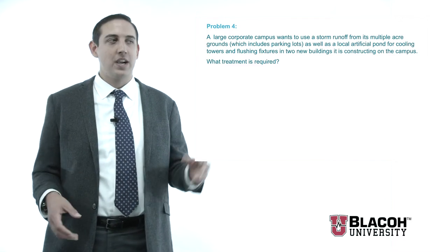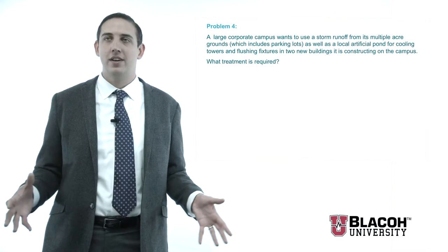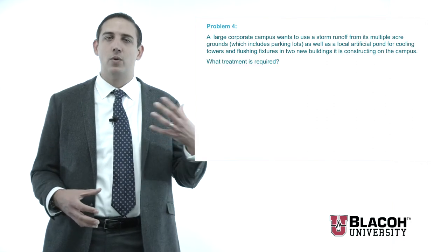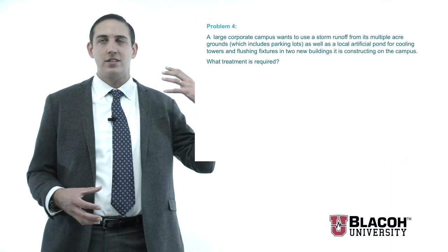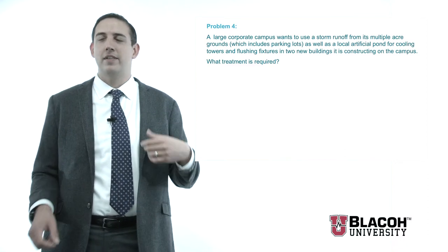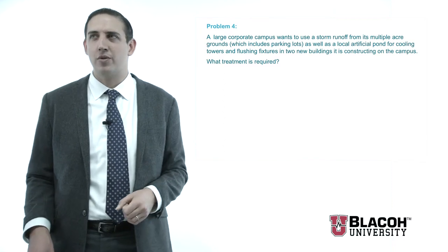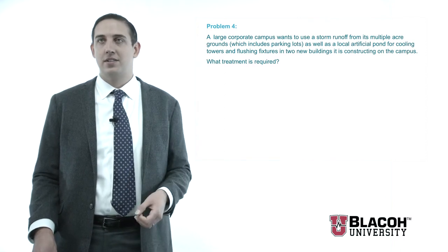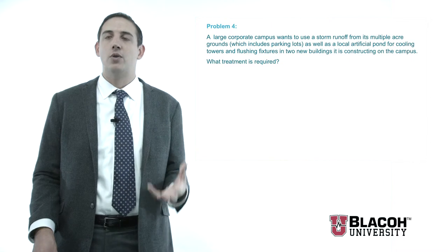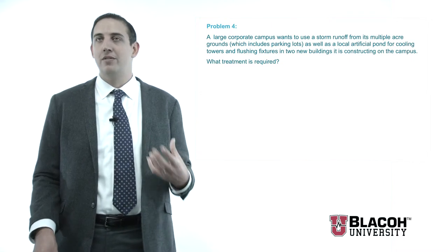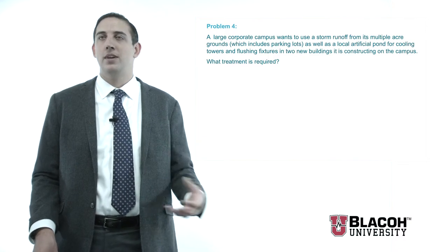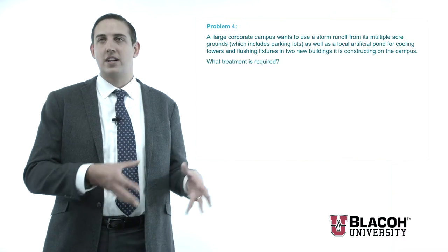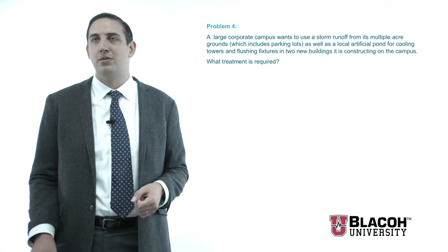So where do we start? I have cooling towers and flushing fixtures. I have a very large area, so just like in our previous example I need to account for the parking lots — you're going to see a lot of oils, emulsions, and road treatment chemicals. This is in a northern area of the country so you will see quite a bit of de-icer use. You also have large grass areas, where your runoff coefficient will be much lower — around 0.5 instead of 0.9 or 1.0 — so you won't capture as much water proportionally, but you have a very large total area to work with.